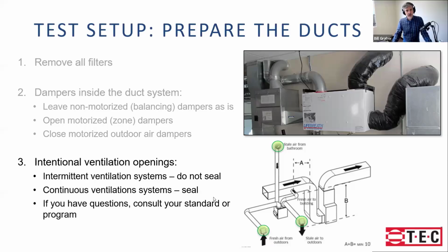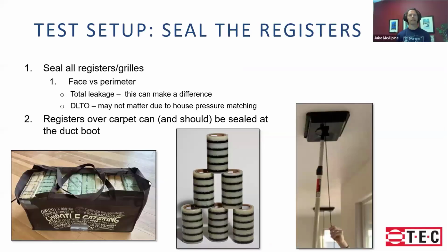I'm just going to reiterate, Jake, because you've pounded this into me and it's really helped me. Think about these tests not as saying what's happening when it's operating, but instead saying, I'm going to set this up so I can test for a quality sealing of these ducts. And that really helped me say, oh, I understand now why we're doing this. We're not trying to reflect how it does when it's operating. How am I going to set this up so I can get a good test of, yes, this ductwork is sealed well. Yep, exactly.